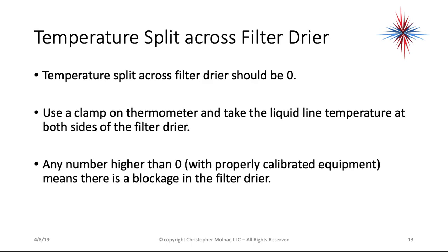Another important number that a lot of people miss is the temperature split across the filter dryer — it should be 0. Use a clamp-on thermometer and take the liquid line temperature at both sides of the filter dryer. Any number higher than 0 with properly calibrated equipment means there's a blockage in the filter dryer.